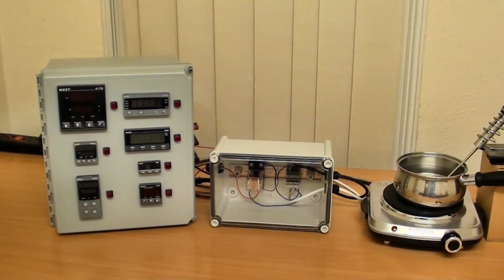We have a P6100 controller fitted with an output relay for control and a hot plate to heat up the water. The relay has a current rating of 2 amps. The hot plate will be drawing more than 2 amps, so consequently the output relay of the controller is connected to an interposing relay here to deliver the higher current required by the hot plate.